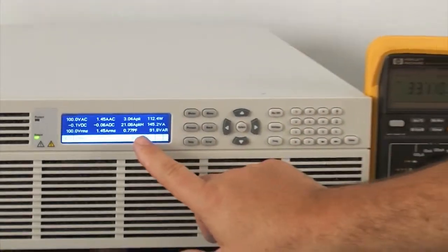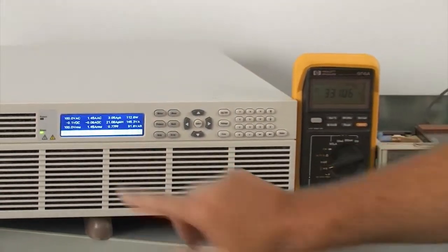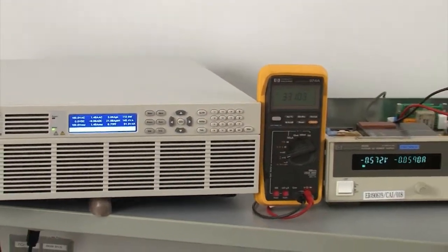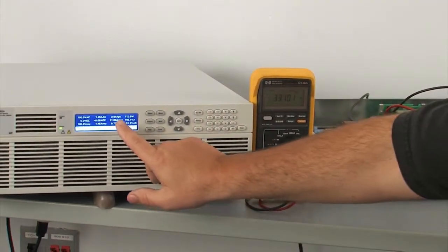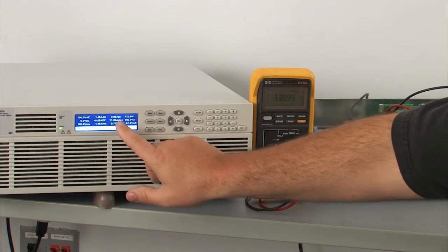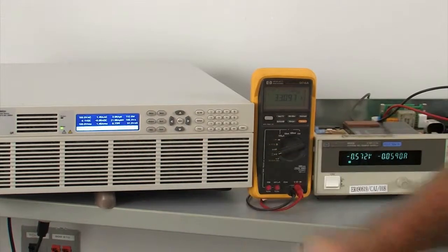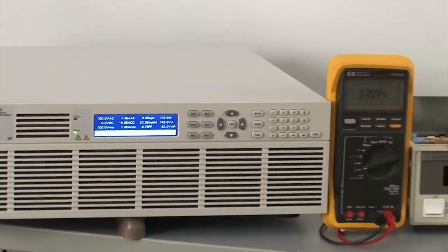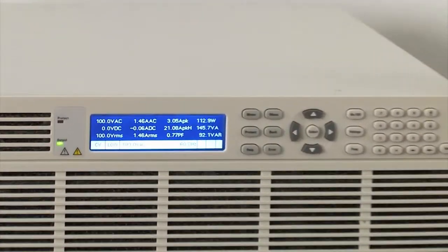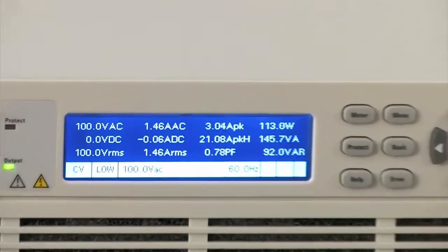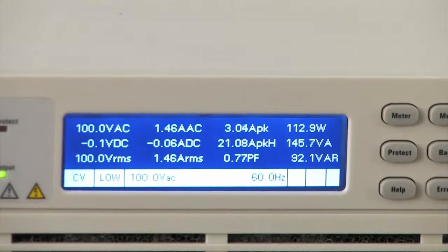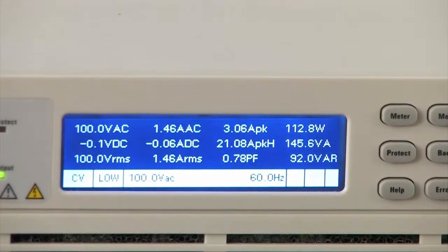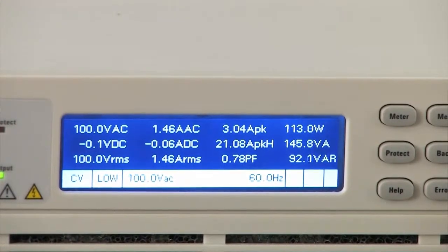Over in the screen here, shown below, is the actual peak current inrush. That's a hold function, so it actually measures the peak current that's occurred at any time during the last cycle until I clear that number.